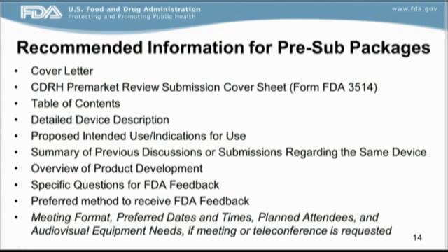For an in vitro diagnostic device, this should also include a detailed draft of the intended use of the device, including the intended use population, the analyte or condition to detect, and the assay methodology. Sponsors should also include a summary of previous discussions with the FDA regarding this device, including the submission numbers, as well as an overview of the product development, including an outline of non-clinical and clinical testing, either planned or already completed. Importantly, a pre-sub should include specific questions regarding review issues relevant to a planned IDE or marketing application.